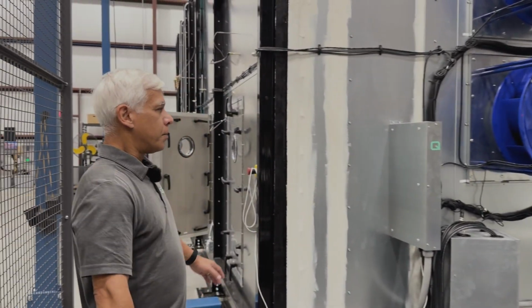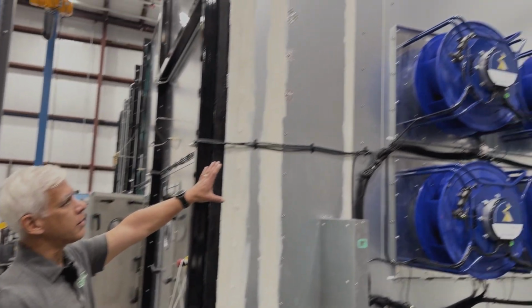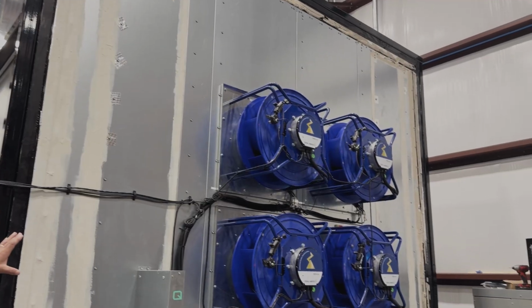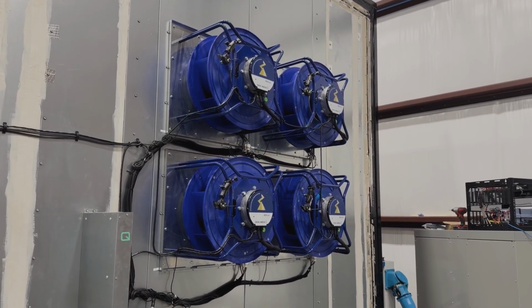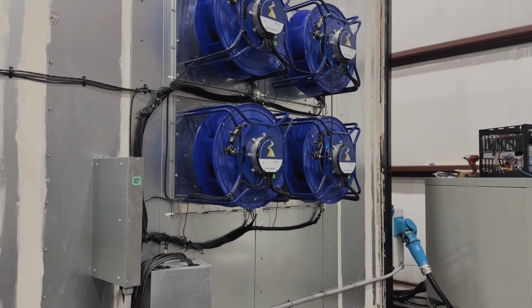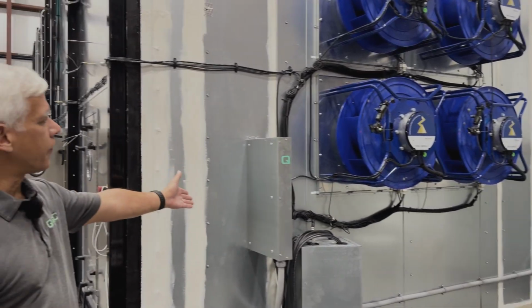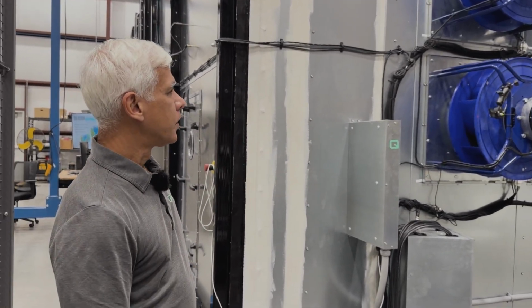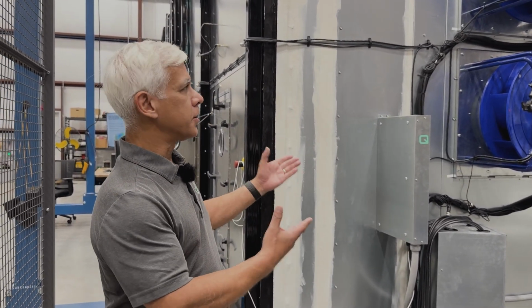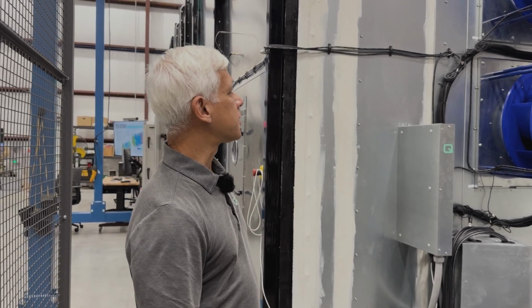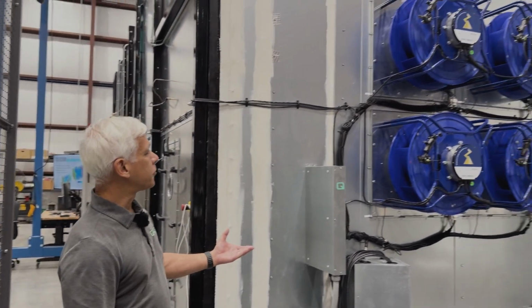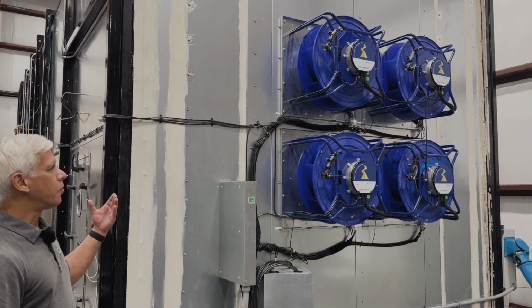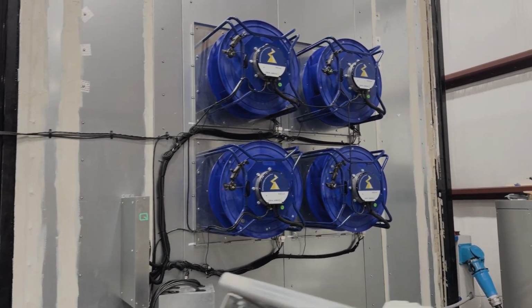But what we're looking at here is a set of 4 test fans that is similar to what you'd find in a multi-motor plenum fan. We have the Q-PAC fan controller here. So this is the test fan. This is the equipment under test. This is what we'll be measuring the performance of, what we'll be doing experimentation on.